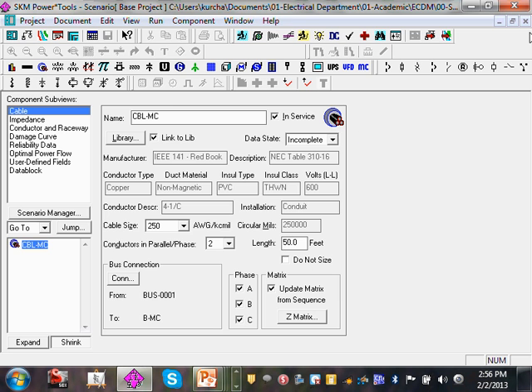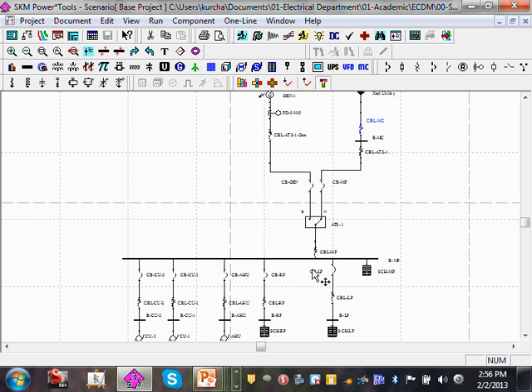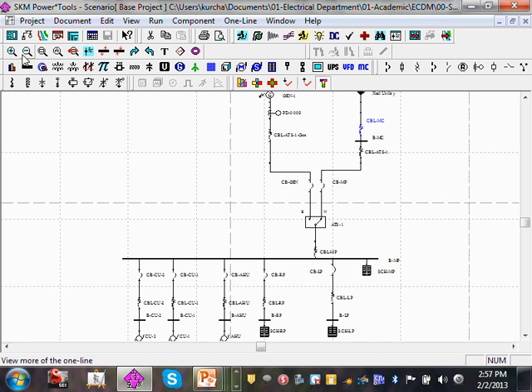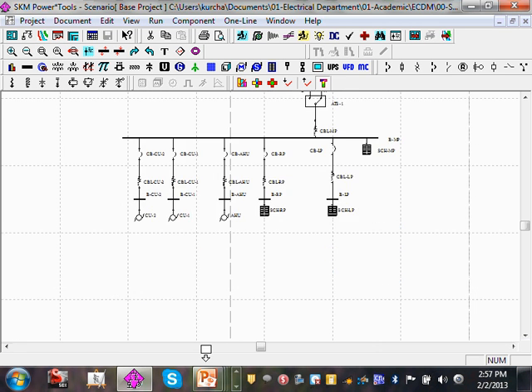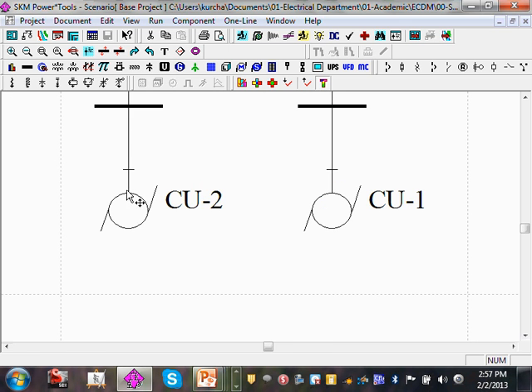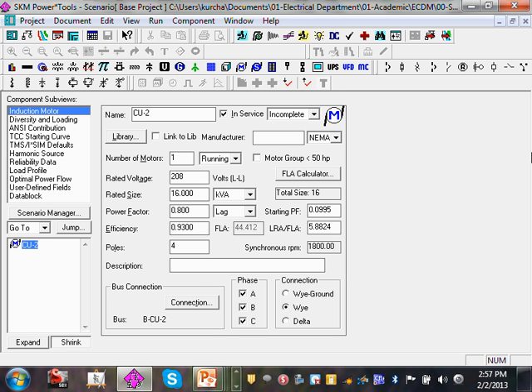I'm showing you this one because when I show you the calculation, it's coming here. I'm going to go back, guys, into the chiller here and show you how you model the system. Zoom all and model your system here. Here's my cooling unit. My cooling unit here happens to be 16 kVA. Here's the power factor for it. And then you model all your equipment.